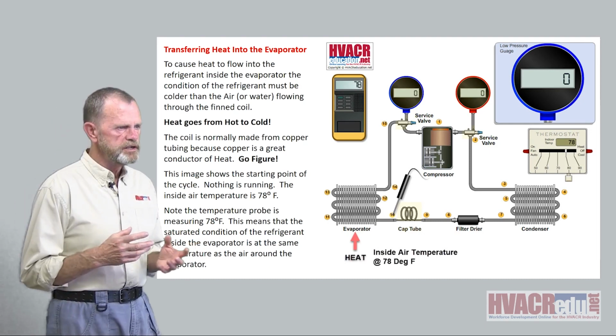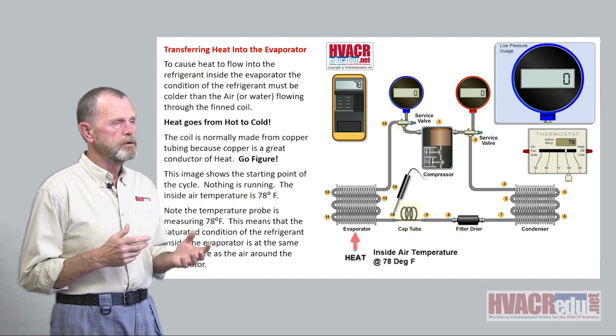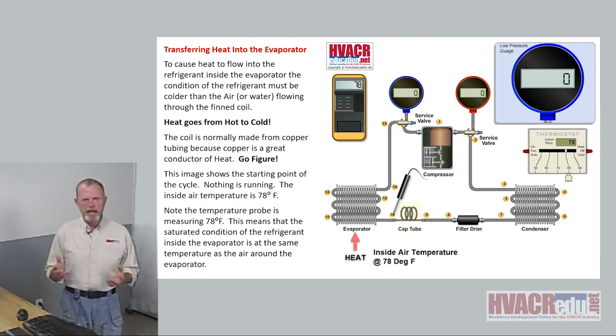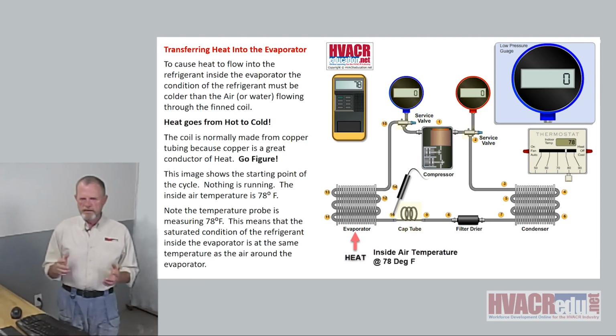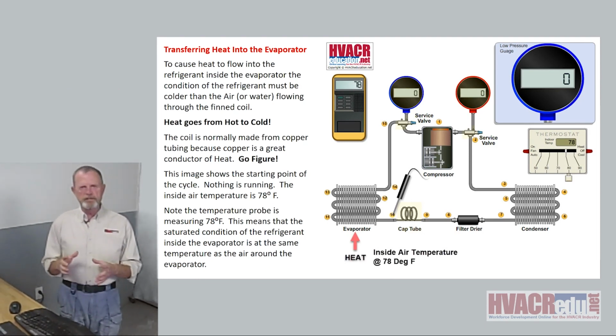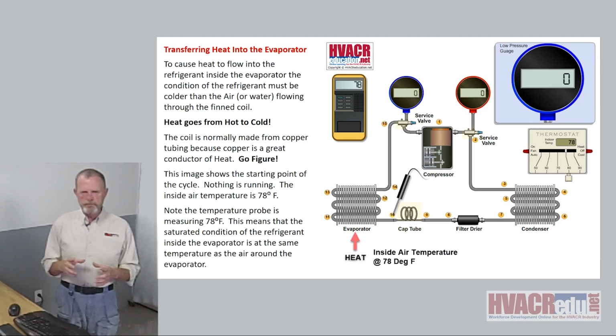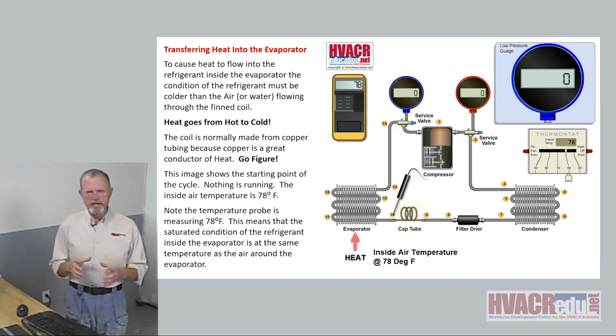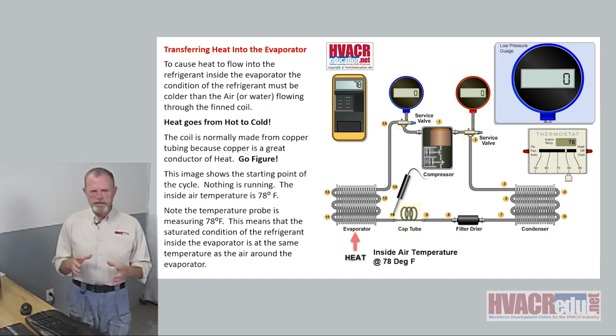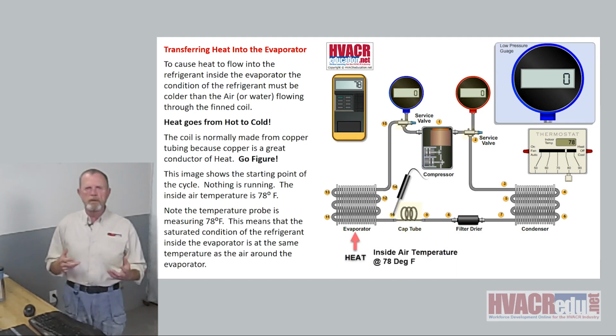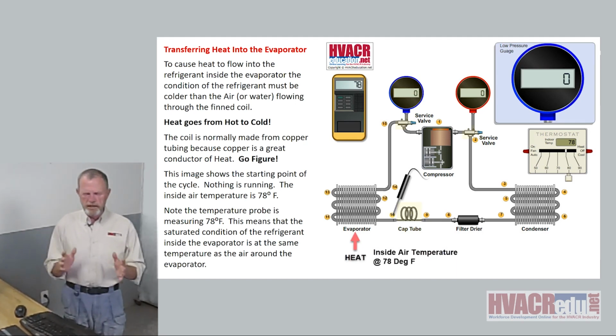A refrigerant is a great measuring device, if you will, to tell you what temperature the ambient is. If I have 78 degree air around a refrigerant tank, the pressure temperature relationship of the tank will be at 78 degrees because it's in a saturated condition. There's no pump. Nothing is happening. It's just sitting there static.